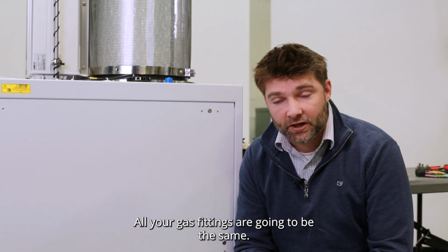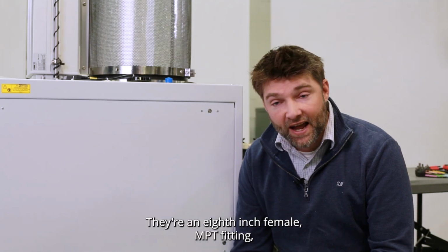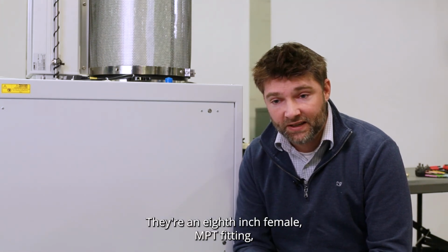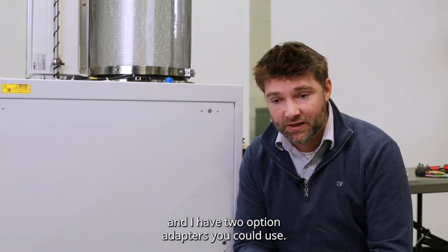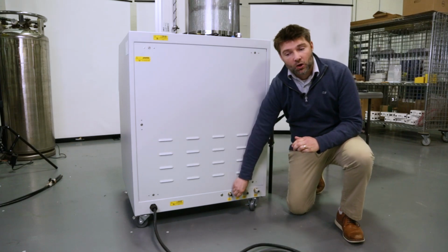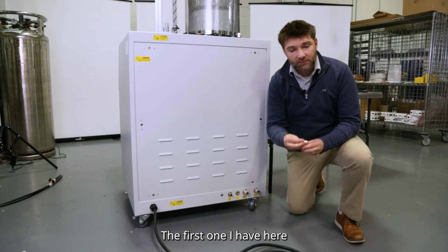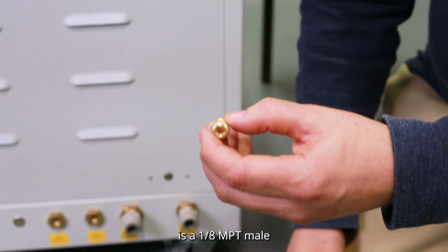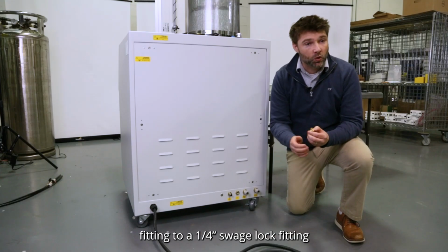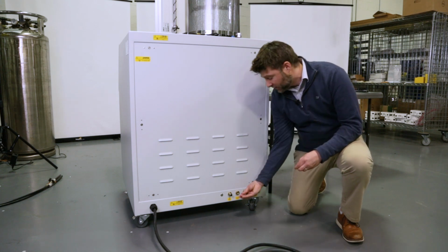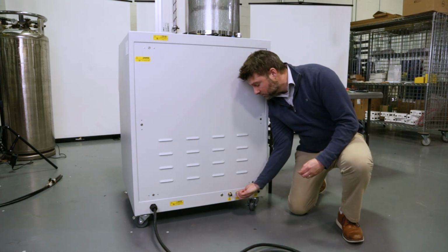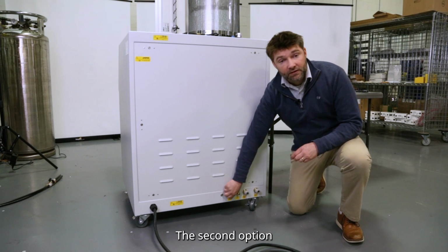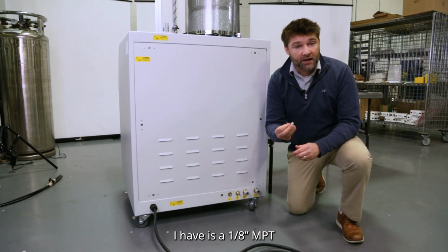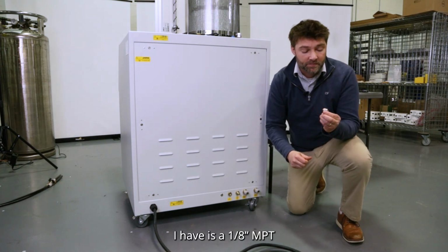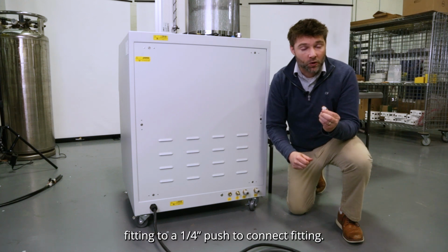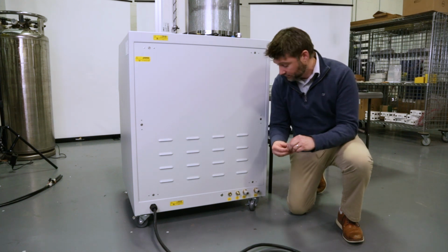All your gas fittings are going to be the same. They're a 1/8-inch female MPT fitting, and I have 2 option adapters you could use. The first one I have here is a 1/8 NPT male fitting to a 1/4-inch Swagelok fitting. The second option I have is a 1/8-inch MPT fitting to a 1/4-inch push-to-connect fitting.